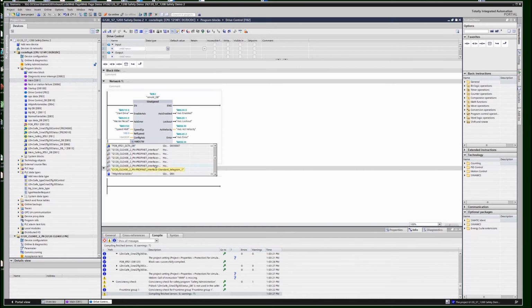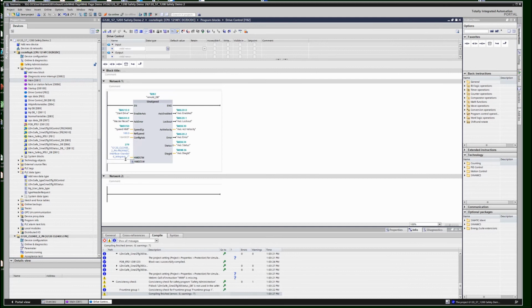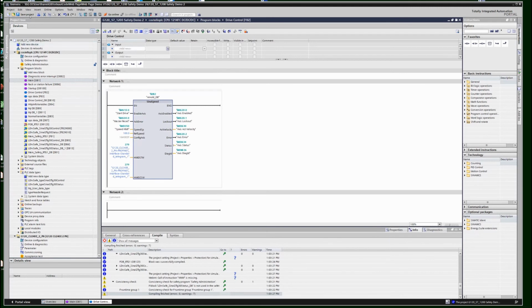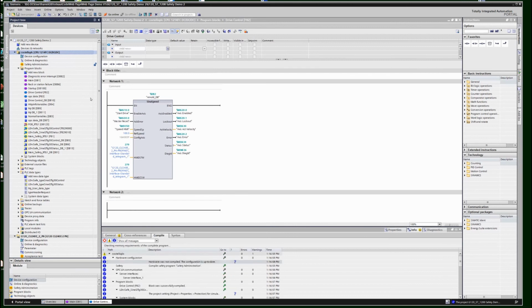If you highlight over here, you can see that this is the normal telegram, not the safety. We already did the safety. It's got a pretty long name, or you can just use that number, 279. The nice thing about this is if you move the addresses around later, that number is automatically updated in the pointer, and you don't have to go back through your program and find each time you've used this and change it.